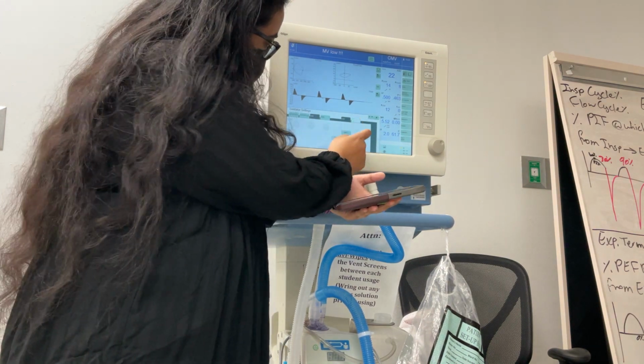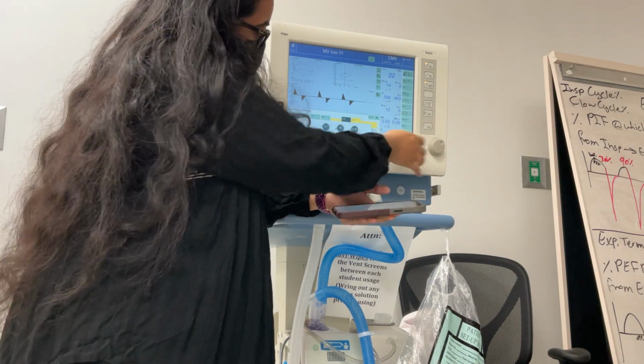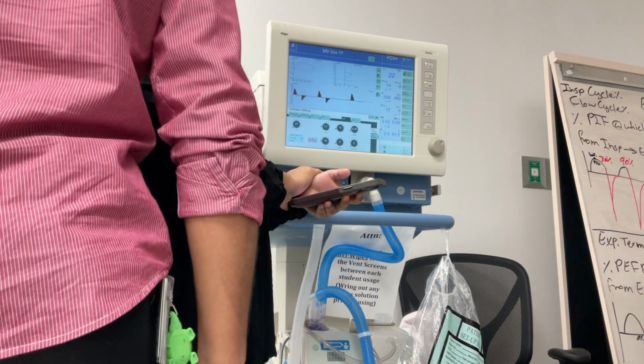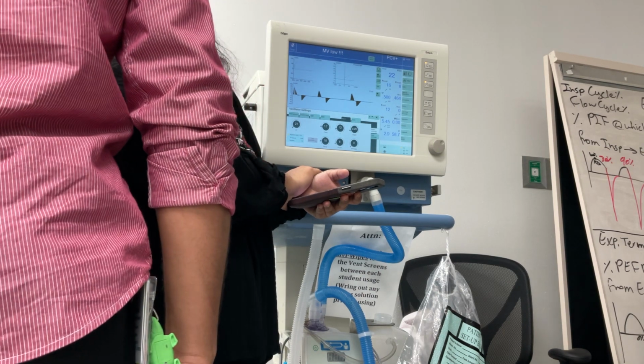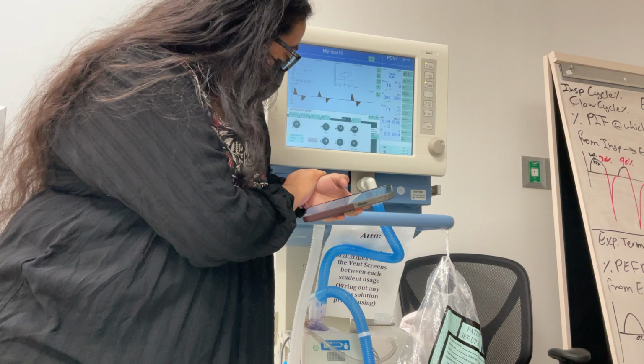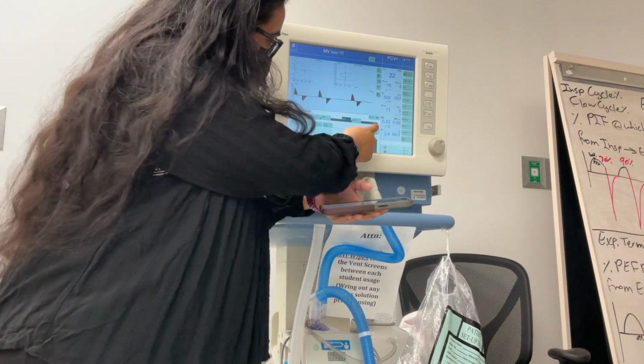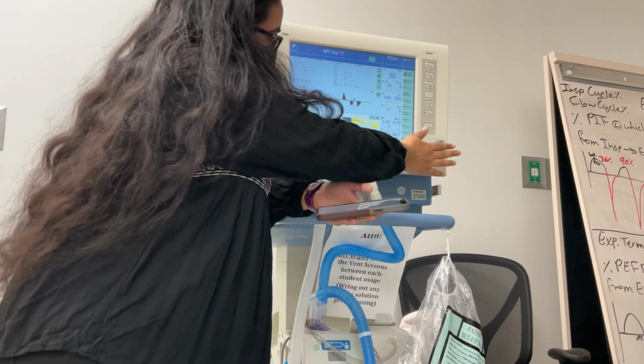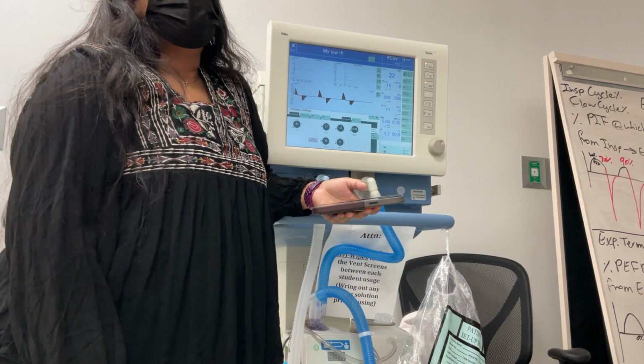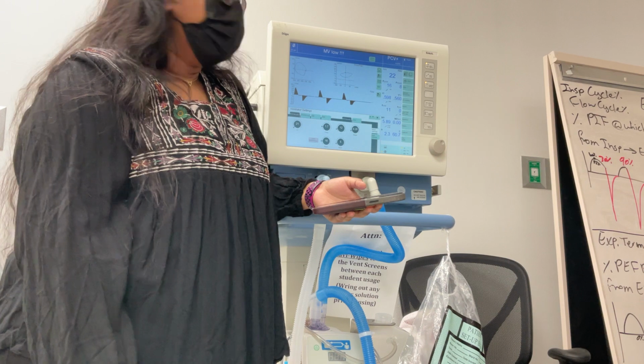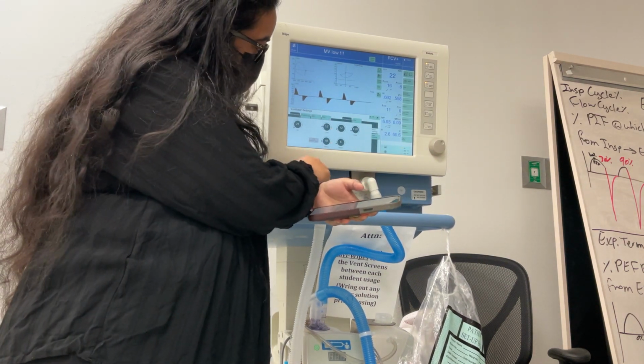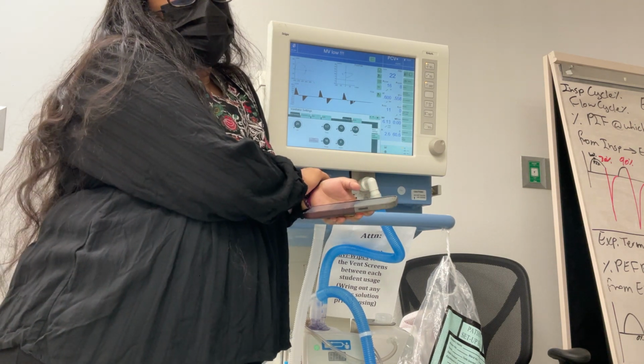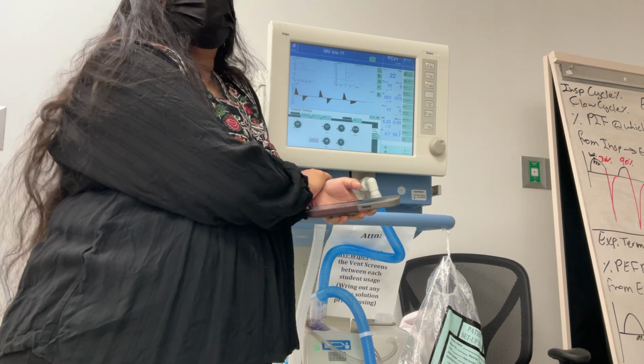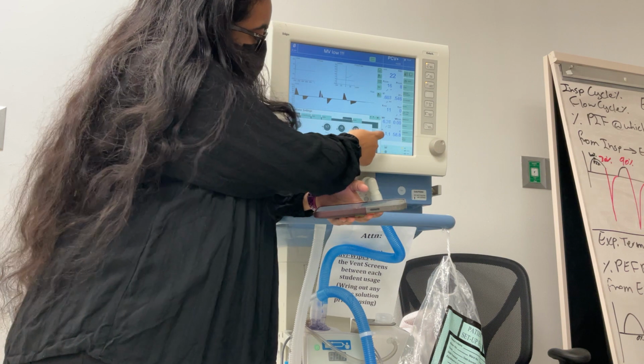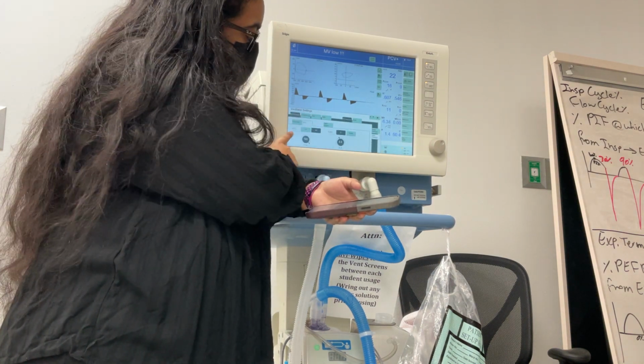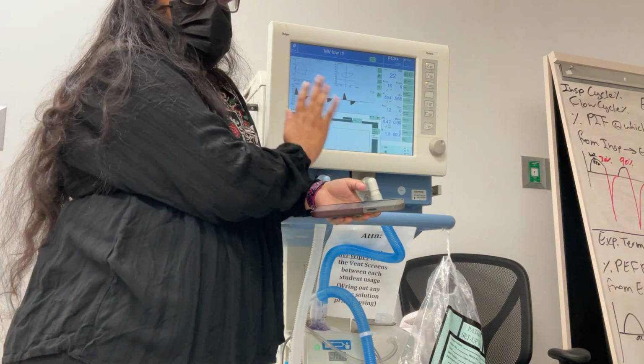Next we'll go to PCV Plus. Y'all know what PCV Plus is? Start with PCV Plus Assist. Do y'all know what PCV Plus Assist is? Yeah. So same stuff as normal PC-AC, okay? Nothing different there. You'll set up your settings here: FiO2, I time, your rate, slope. What is slope on here? Which is how fast to hit. And you've got your inspiratory pressure and your peak. Additional settings on here is always going to be your tubing compensation and your trigger. So nothing special under PC-AC.